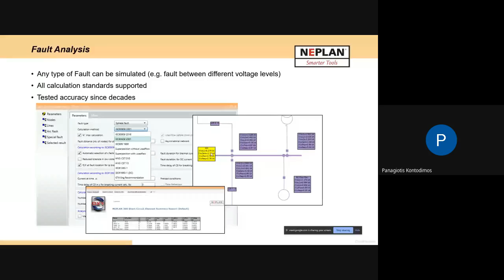We have provision for new components, for example when we have converters, like a machine feeding the network through a converter. Then we can simulate if there is contribution from the converter - we can model this and simulate it. Of course, here we follow the standards, this is defined, for example, in IEC standard. The point is that we are constantly integrating new technologies into the calculation.